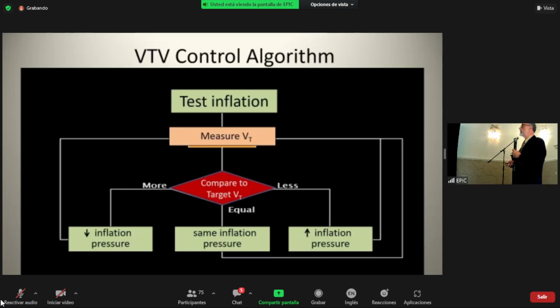Certainly PRVC and volume guarantee work by these algorithms, where there's an initial pressure generated. The resulting tidal volume is measured, and it's compared to the target. And if that measured tidal volume is below target, the inflation pressure goes up. If it's close to target, no change. And if it's above the target, the inflation pressure will come down. And so there is always a little delay in getting the tidal volume exactly where it's targeted.